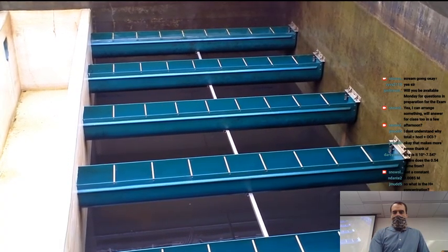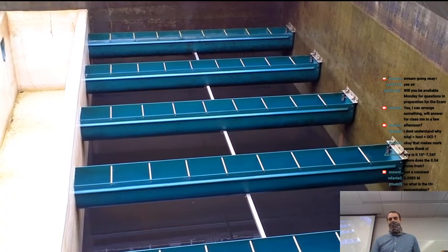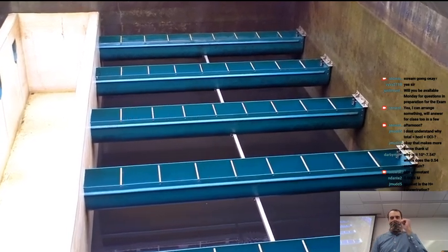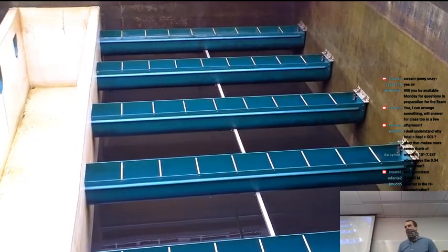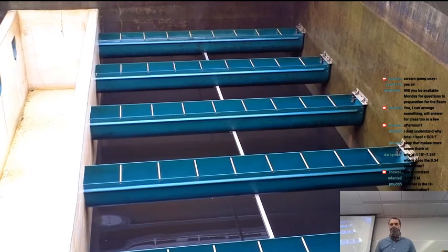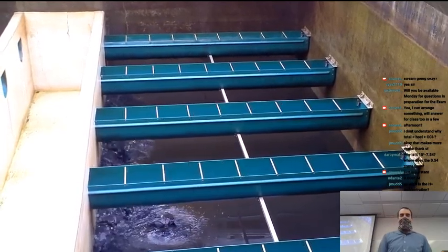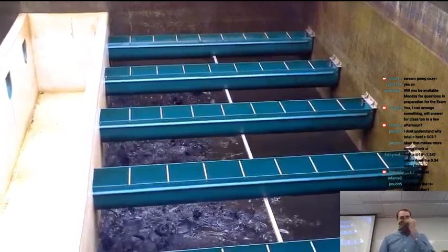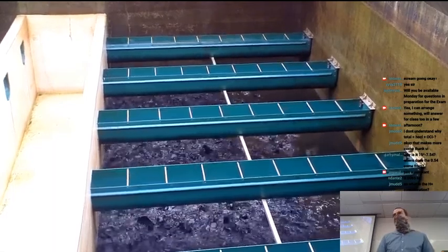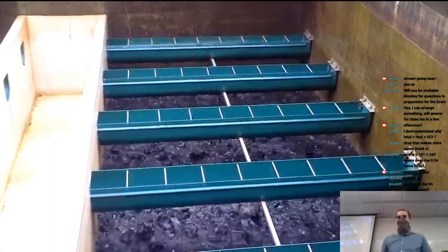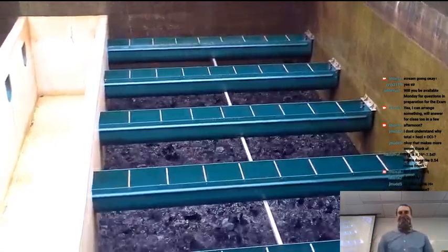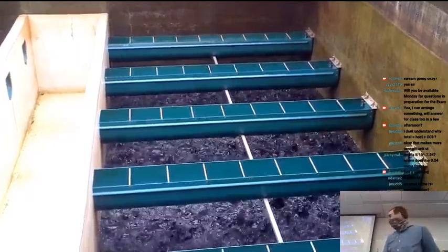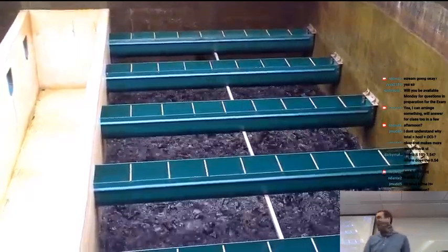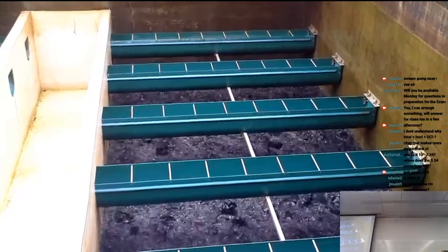So here's a wastewater treatment plant, or excuse me, a drinking water treatment plant. This is a bed where they stopped production, and they probably let it settle for a little while, and now they're backwashing. So you can see all that nasty looking water coming back through. They're pumping clean water back up through the system. This is going to go on for several minutes. I'm going to turn down the light so you can get an even better image.